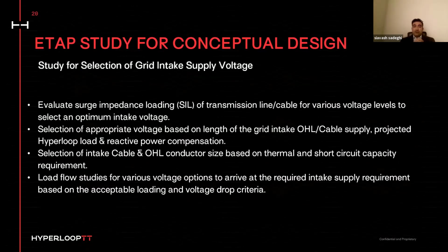ETAP, a study for conceptual design, a study for selection of grid intake supply voltage, is another task for ETAP, basically to evaluate surge impedance loading of transmission line, selection of intake cables and also conductor sizing, cable sizing, considering the thermal and short circuit capacity, load flow analysis for various voltage options to arrive at the required intake supply requirement based on the acceptable loading and voltage drop criteria.